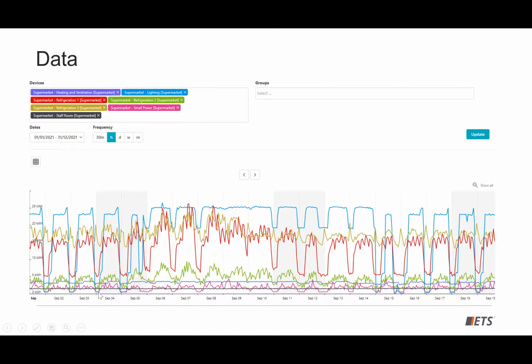When I talk about data, this is the sort of data my teams and I look at—we get quite geeky over it. We'd look straight away at all those squiggly lines on the chart. In the middle, around the 8th to 10th of September, you'll see the red line go up, up, up, and then drop to a very low point before staying fairly high for that period. We'd say something has been left on, something's happened here—equipment not working accurately, something left on.